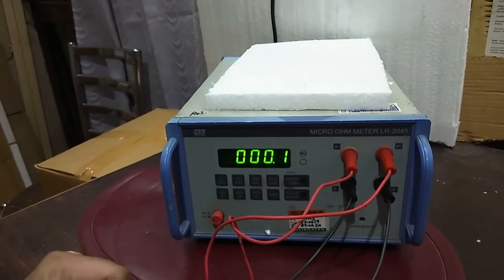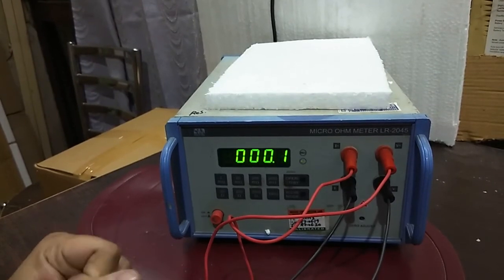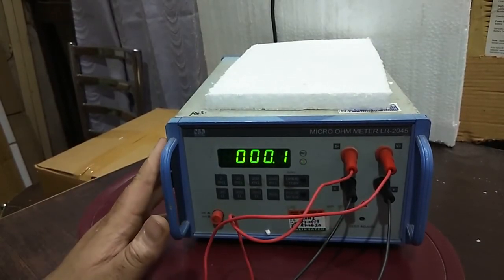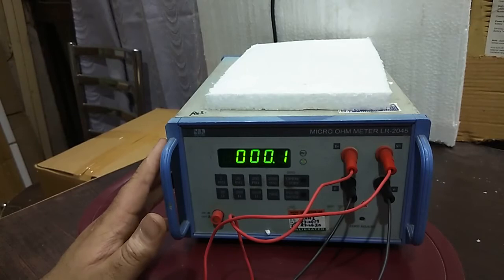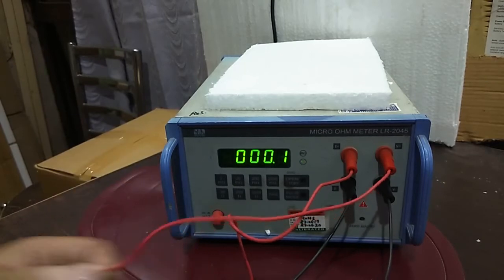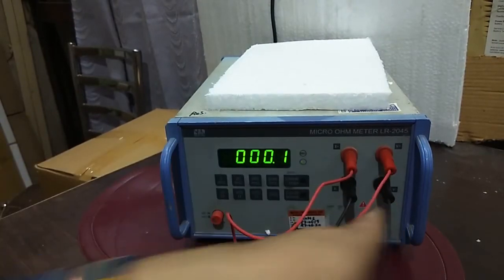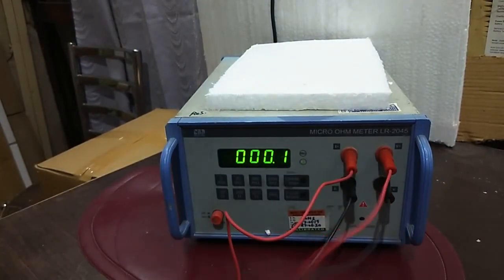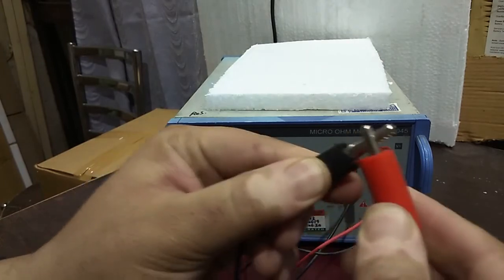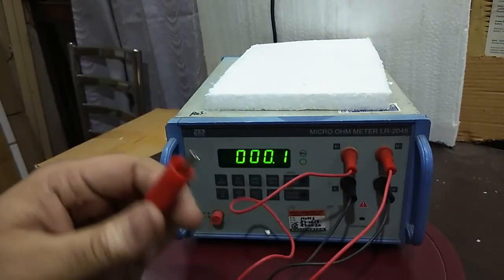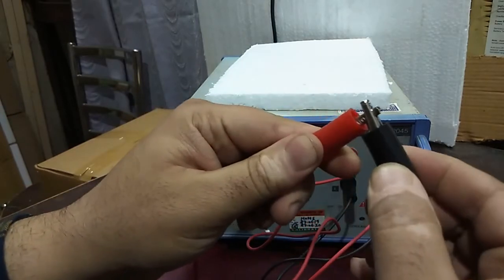Previously I was telling you how to set zero. I will be showing you how to set zero in this Motwani make micro ohm meter. Firstly we have to short this V plus point to the V minus point like that, and then I plus point to the I minus point like that.